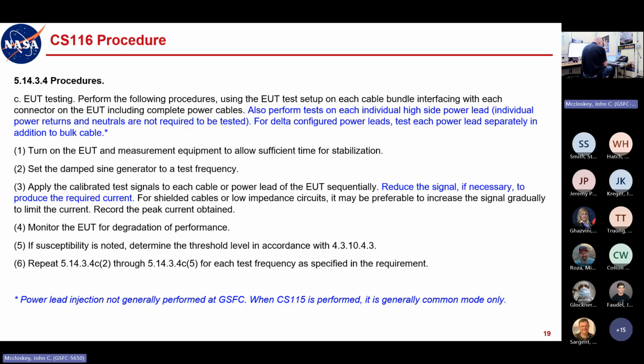One other thing I'll point out here that's somewhat unique to this test. Most of the time when you do your pre-calibration, the instructions are, I believe this is true for CS115, you do your pre-calibration, then you move the probe out of the fixture, clamp it around your cable, and you inject that pre-calibrated level. And the signal is what it is. Here with CS116, that highlighted blue statement says reduce the signal if necessary to produce the required current. Remember you're injecting into a controlled impedance fixture of 100 ohms, and when you move the probe over to an actual cable under test, the impedance is most likely going to be different, and it could be lower than that, which means you could get more current than what you've pre-calibrated. Now you're going to be limited by the 50 ohm source impedance of your signal source. So it's not going to go through the roof, but it could go to a factor of 2 or 3 times your pre-calibrated signal level.